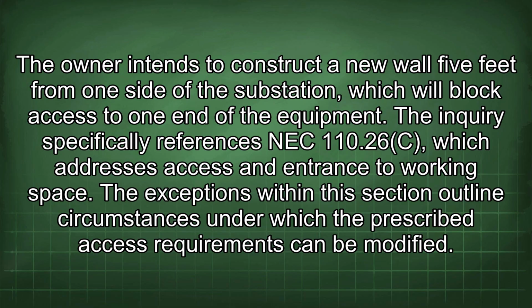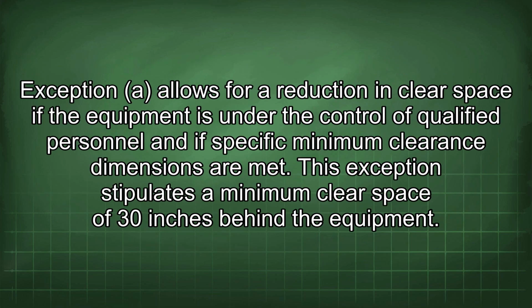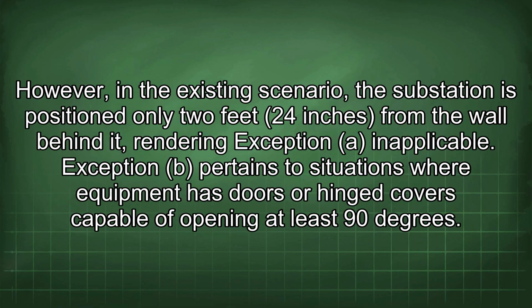The inquiry specifically references NEC 110.26(C), which addresses access and entrance to working space. The exceptions within this section outline circumstances under which the prescribed access requirements can be modified. Exception A allows for reduction in clear space if the equipment is under the control of qualified personnel and if specific minimum clearance dimensions are met. This exception stipulates a minimum clear space of 30 inches behind the equipment.